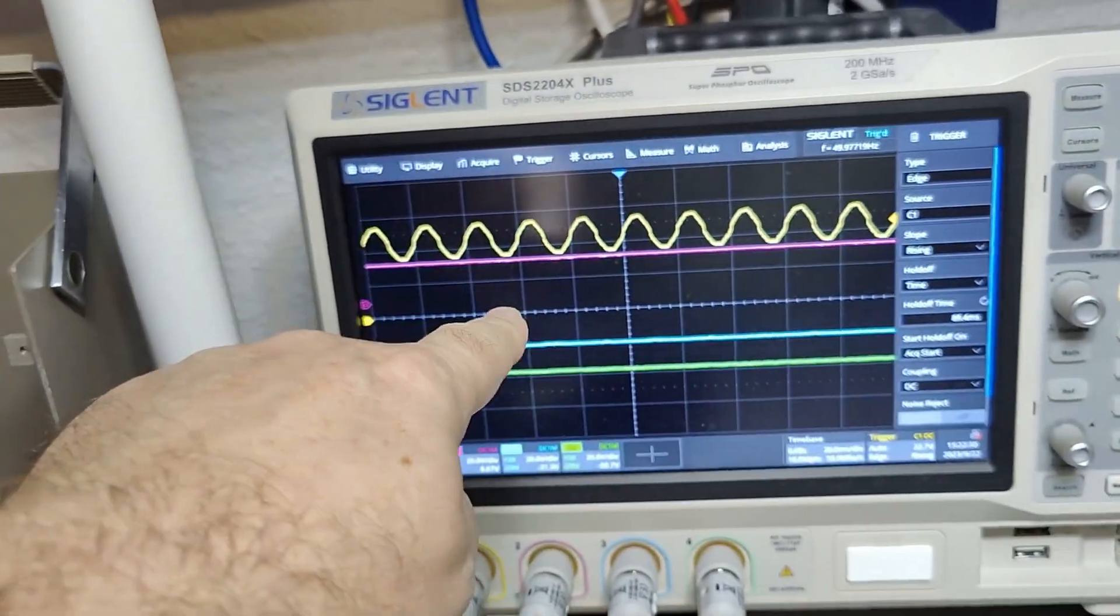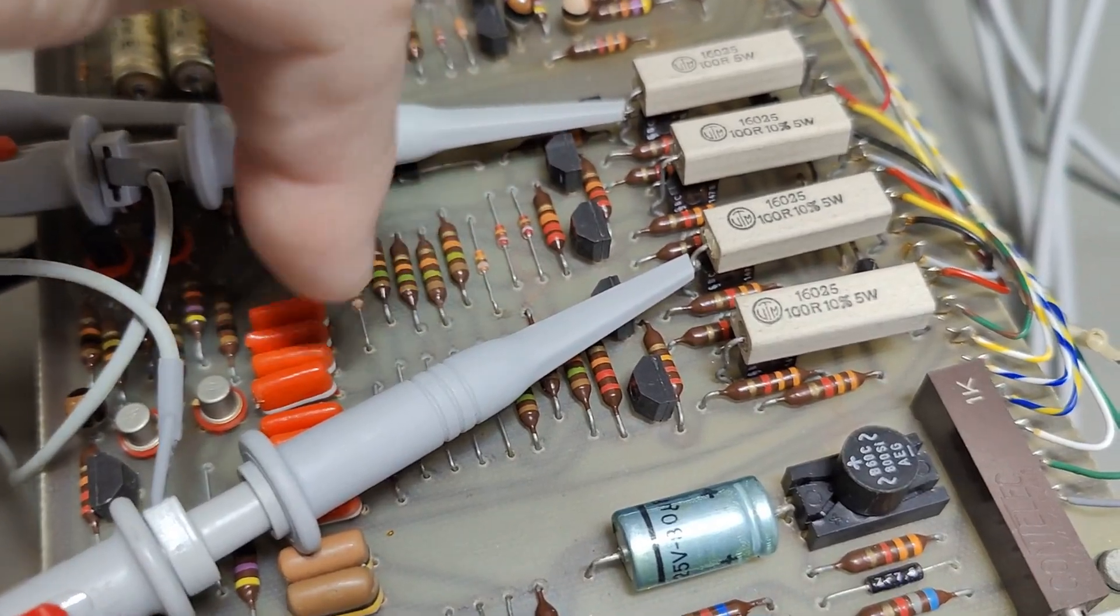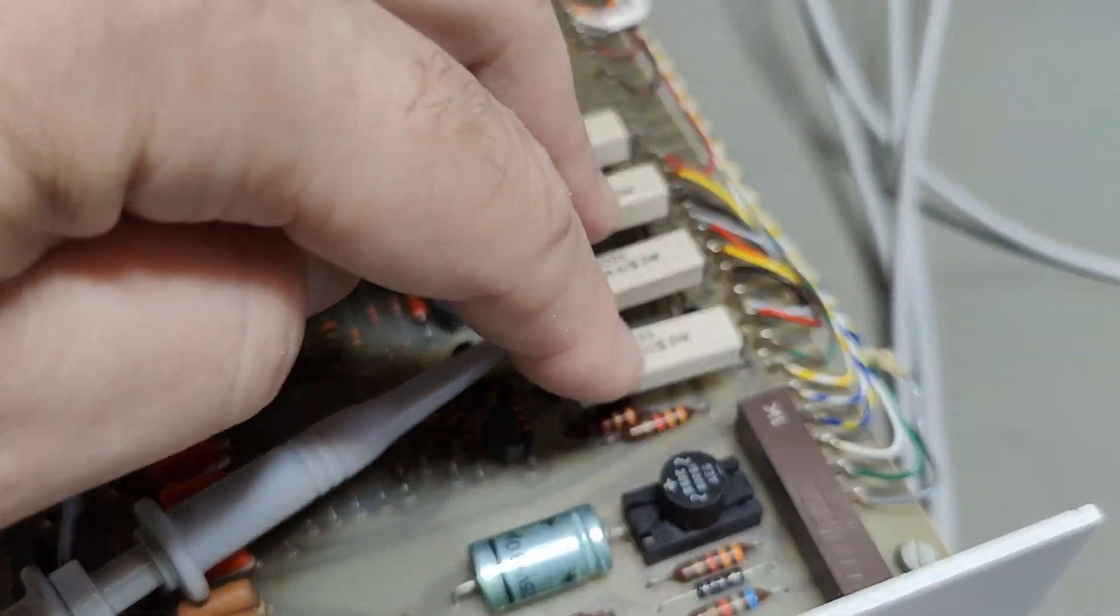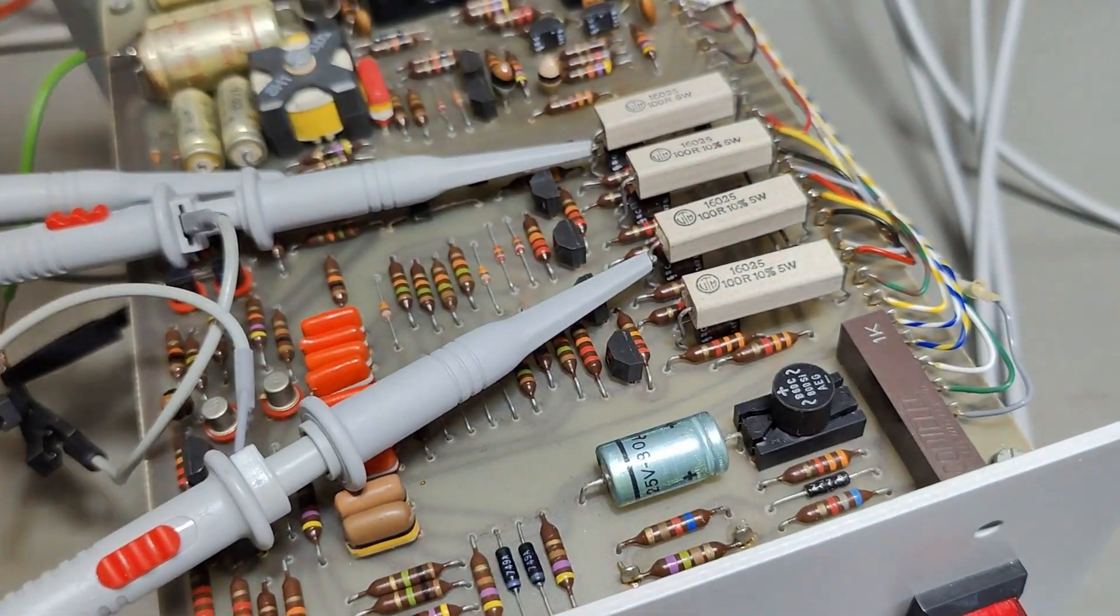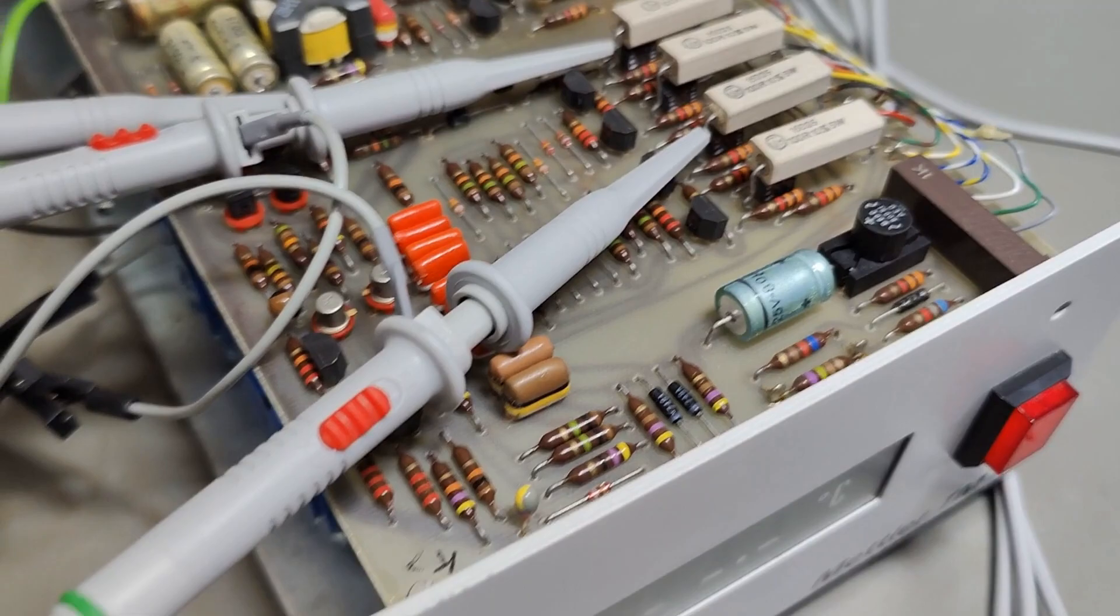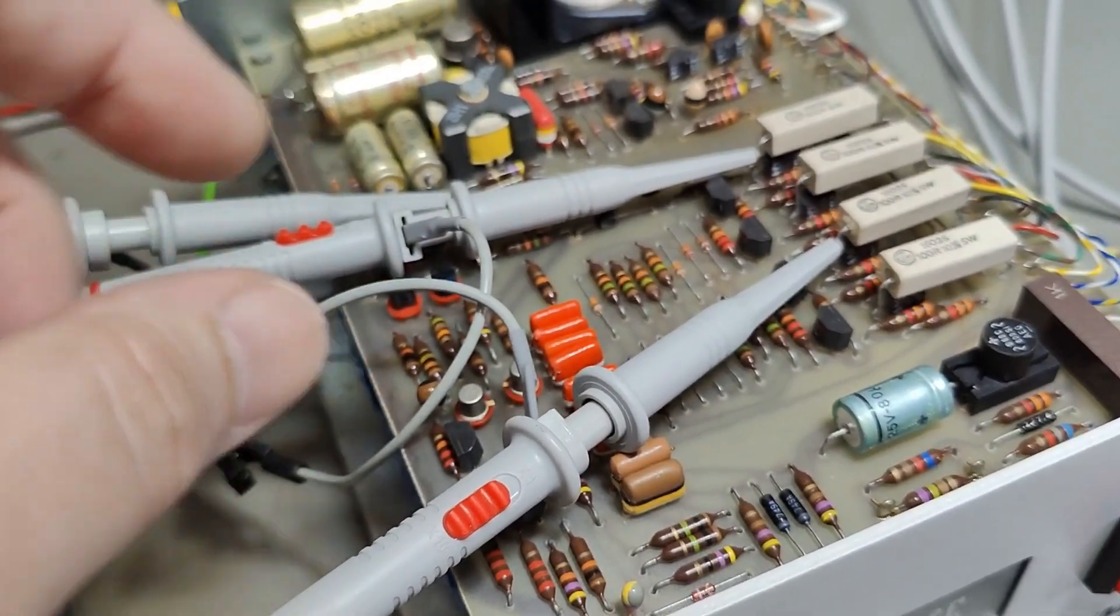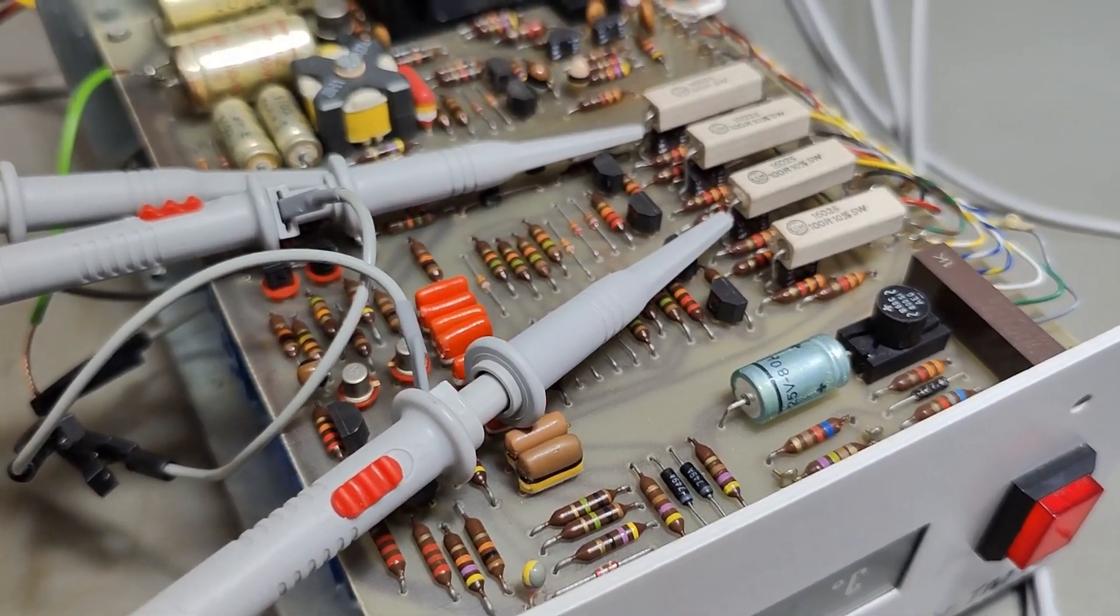The resistor bridge for the PT100 resistor, and the other resistor in that bridge is of course the reference potentiometer that is moved by the motor and gearbox. So it's trying to make the measured voltage and the potentiometer voltage exactly the same. So what they're doing is they take this AC voltage that they're driving the bridge with and compare with a square wave signal. Is it before or is it after and then they count up or count down? So those are the counters and they're driving this system with diodes that makes the system of pulses that drives the motor in the right phases in a certain pattern that makes the movement of the motor correct. So that's all there is to it. Really, there isn't any fancy smancy regulations and stuff like that. Probably some of those capacitors here will form a filter that just add a little bit of hysteresis or how aggressive it is and stuff like that, but that's all really.